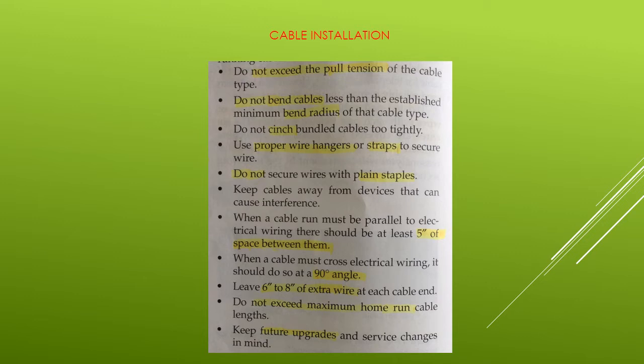Keep cables away from devices that can cause interference. When a cable run must be parallel to electrical wiring, there should be at least 5 inches of space between them. When a cable must cross electrical wiring, it should do so at a 90 degree angle or perpendicular. Leave 6 inches to 8 inches of extra wire at each cable end, and do not exceed maximum home run cable lengths. Finally, keep future upgrades and service changes in mind.